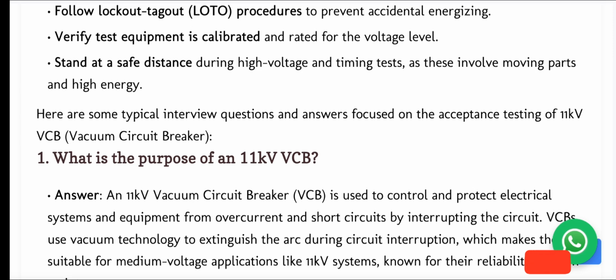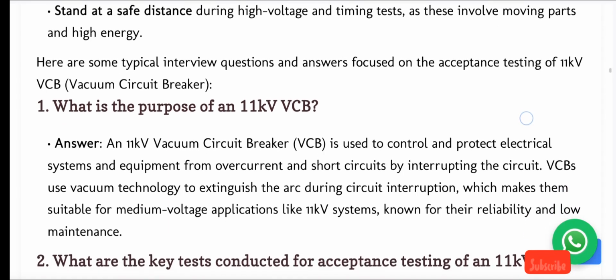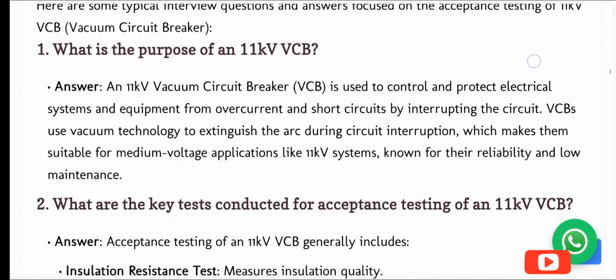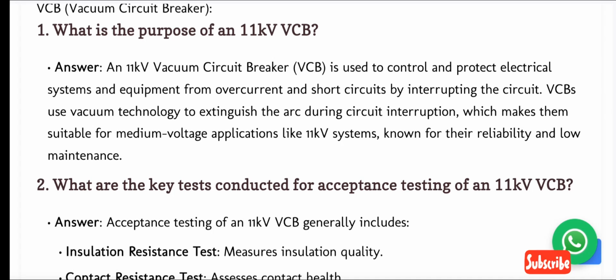Here are some typical interview questions and answers focused on the acceptance testing of 11 kV VCB vacuum circuit breaker. 1. What is the purpose of an 11 kV VCB? Answer. An 11 kV vacuum circuit breaker (VCB) is used to control and protect electrical systems and equipment from overcurrent and short circuits by interrupting the circuit. VCBs use vacuum technology to extinguish the arc during circuit interruption, which makes them suitable for medium voltage applications like 11 kV systems, known for their reliability and low maintenance.